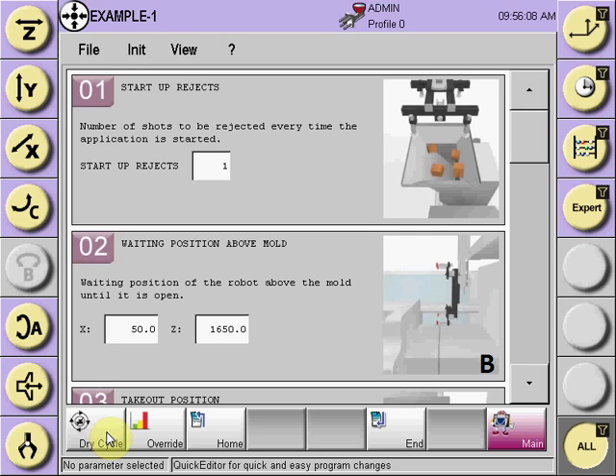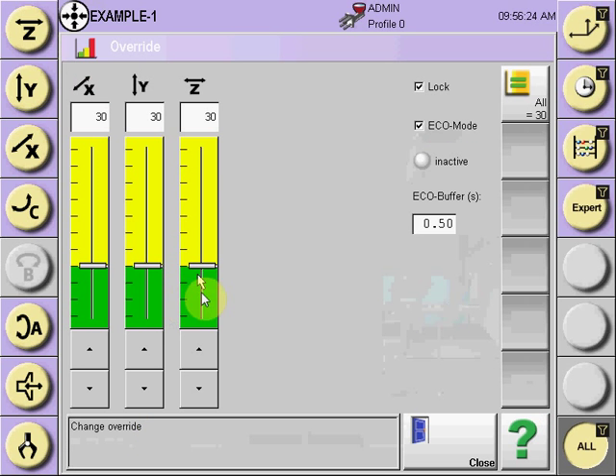Select the dry cycle button. At that time, the override will default to 30%, so it will be dry cycling at a slower speed, which is adjustable via the override by selecting the override button and moving it from 30% up to a higher rate of speed if desired. Remember, while dry cycling we are testing the positions, so the slowest speed is recommended.